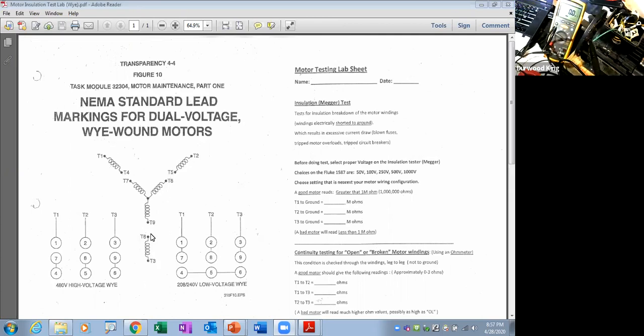It's going to give you the internal resistance of the motor, and it's going to tell you if all 3 readings are the same, like from here to here, here to here, and here to here. If you do those 3 resistance readings through the motor and they're fairly the same, that tells you that the windings are in the same condition, okay? Or they're healthy. If you have an open circuit from 1 to 3, but you get a good resistance from 1 to 2, you've actually got a broken winding in here somewhere or a wire nut has come off, okay? That makes sense? Yes, sir.